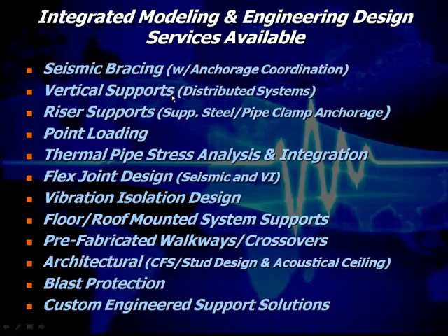We can also do the vertical supports for all the distributed systems, riser supports for the supplemental steel, so that this is not only the modeling, but it's the engineering to back all of this up in accordance with the IBC requirements. So the supplemental steel and pipe clamp anchorages for the pipe risers. We can do all the point loading and show the point loading within the model, and I have an example of that I'll show you.